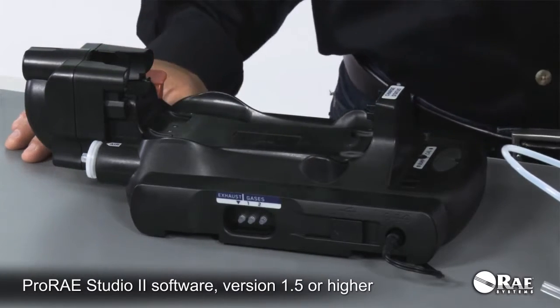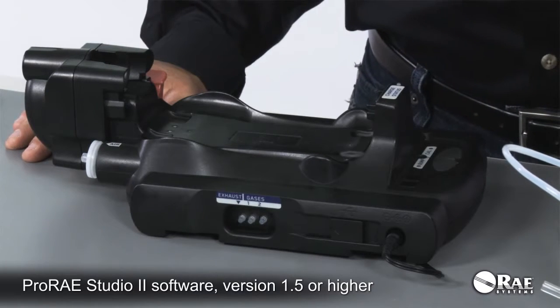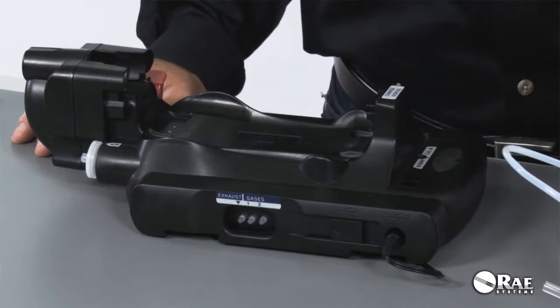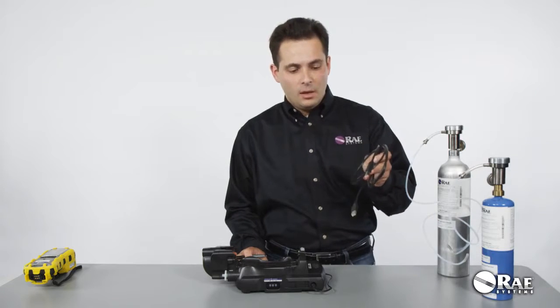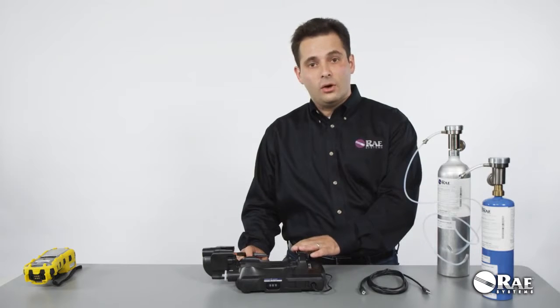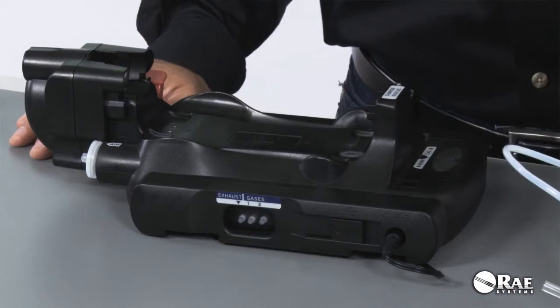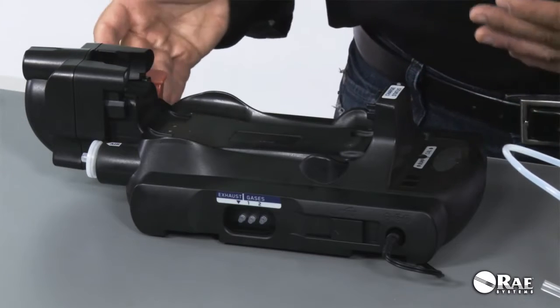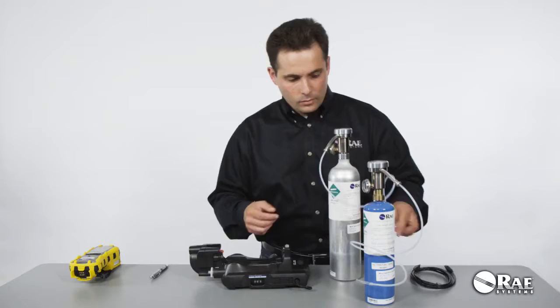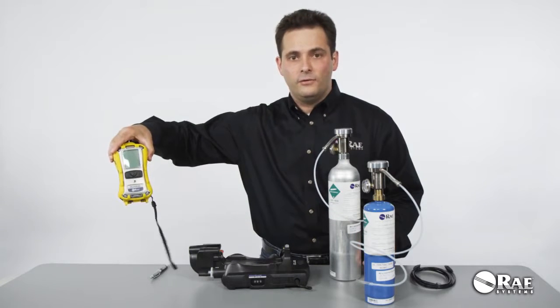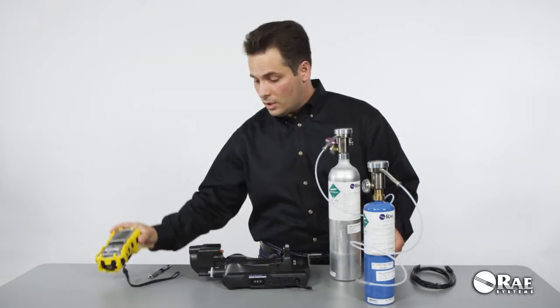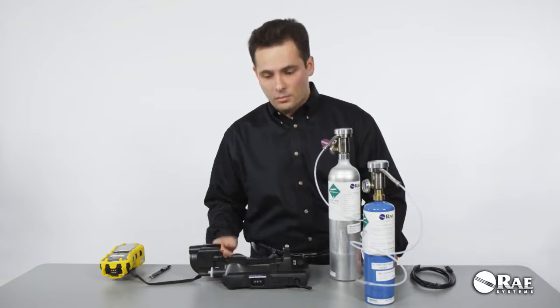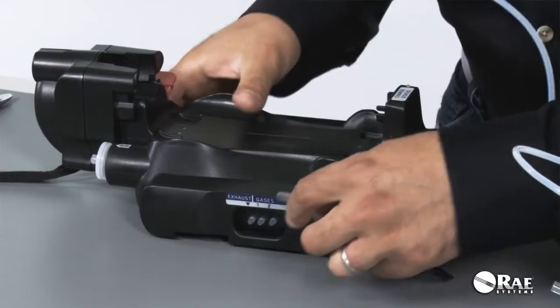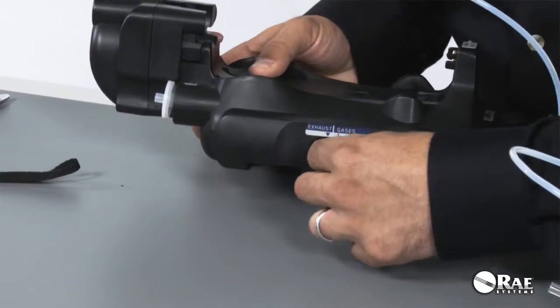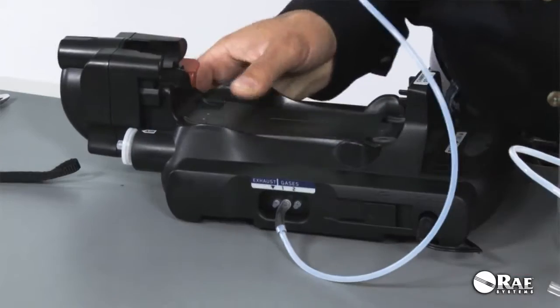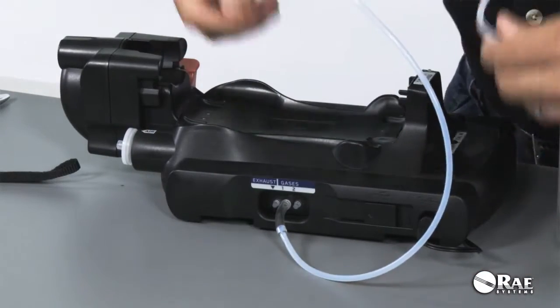The inlets can be configured on a PC using the ProRAE Studio II software. You have to have version 1.5 or higher. There is a PC communications cable that should be used to connect the AutoRAE 2 Cradle to the computer. Once you're done configuring the inlets, make sure to connect the right calibration gas to the right inlet. So for my multi-array, that's a standard configuration multi-array, I'm going to use the default configuration of the inlets. I'm not going to change it. So I'm going to connect the 4-gas mix to the first inlet. And then I will connect isobutylene to the second inlet.